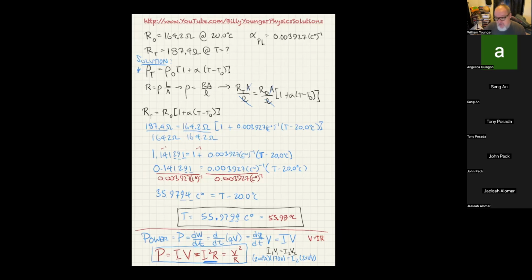That also tells us essentially what the resistance of the wire is going to be, because resistance is rho L over A, and you're either going to use copper or aluminum. Aluminum is lighter but less conductive, not a whole lot less conductive, but a lot less expensive than copper. So you'll probably use aluminum, take the resistivity of aluminum, multiply it by the distance the wires have to travel, then divide by the cross-sectional area of the wires. That resistance is going to be fixed whether you're carrying it at 170 volts or 2 million volts.